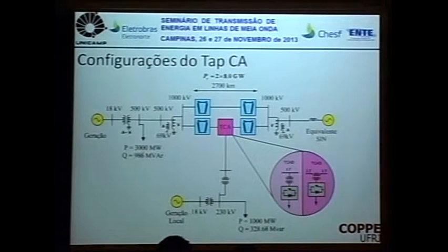This is the system that was assembled in further detail. You can see that there's a small local load. In this circuit, we are considering the 8 gigawatt, 1,000 kV line. So this is a line without direct connections, without tap. The tap is connected here on the line. It can be in shunt or series. The series tap comes from a series transformer. You have power converters doing this work, and through this converting stage with the tap in series, I can have a local generation feeding a local load.